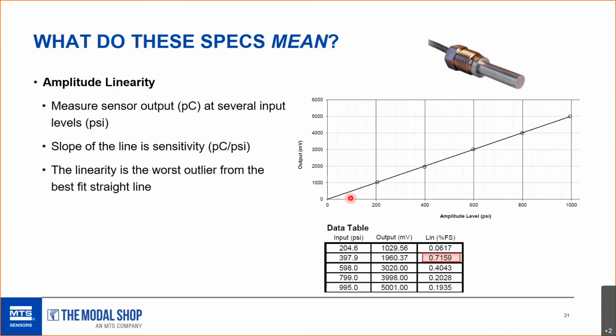We're doing an amplitude linearity sweep where we're testing at 200, 400, 600, 800 and 1,000 PSI, and we measure the voltage output. The actual data we take is not exactly at 200 PSI, but we take 5 averages and average the reference level, and we average the output level, and we calculate a sensitivity based on that. This one happens to be in millivolts.